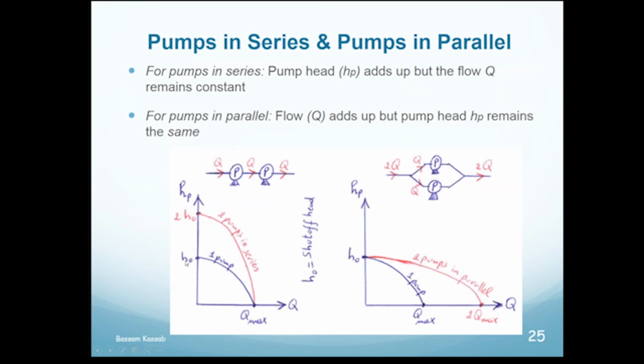And now if you have a system curve, you'll see where it crosses. If the system curve starts here, it will cross there. If your system curve starts here, that means one pump is not enough. That's why you add the second pump, and you will plot the system curve and see where they meet here. So that's the proof that if your system curve starts here, one pump is not going to be enough. You need another one in series.